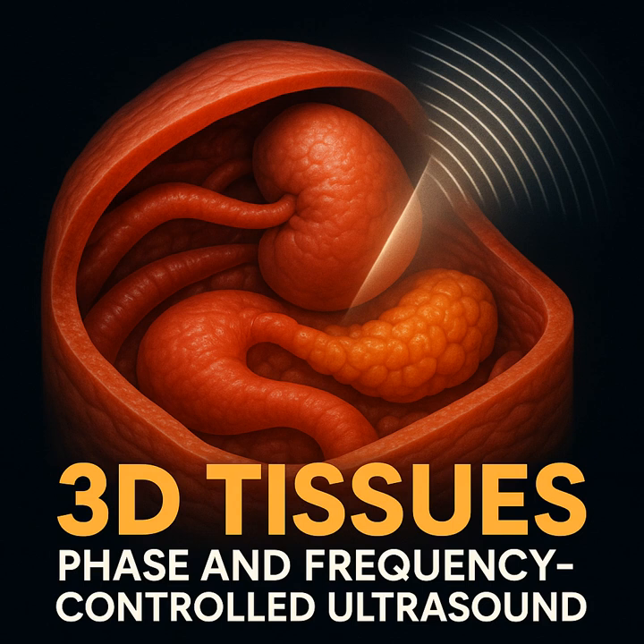Hundreds, sometimes thousands of tiny individual transducer elements on the probe face. And the system can control the timing, the phase, and the strength, the amplitude of the sound waves sent out by each of those tiny elements, just slightly differently. Okay. And what does that let you do? It lets you electronically steer the sound beam. You can focus it, make it narrower, point it in different directions, all without physically moving the probe.